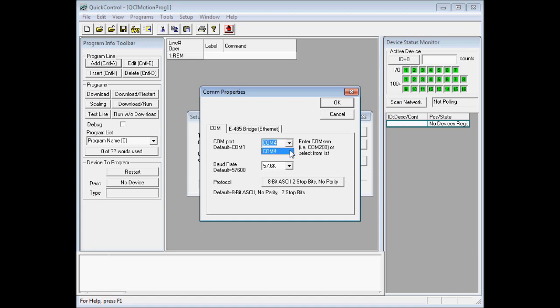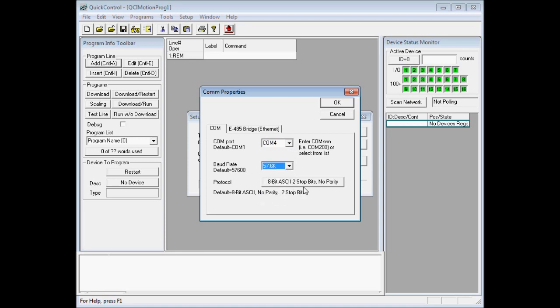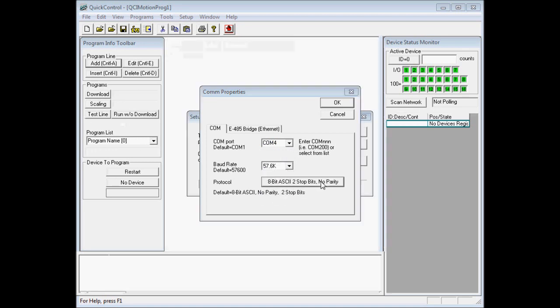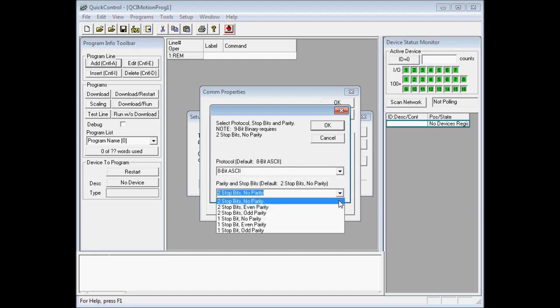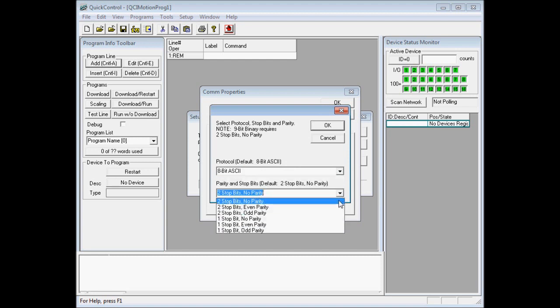Go ahead and select our communication port. My communication port is configured for COM4, so I'll select COM4. The baud rate, I'll select our default baud rate which is 57.6k, and the protocol, I'll select that to our default protocol which is 8-bit ASCII, 2-stop bit, no parity.